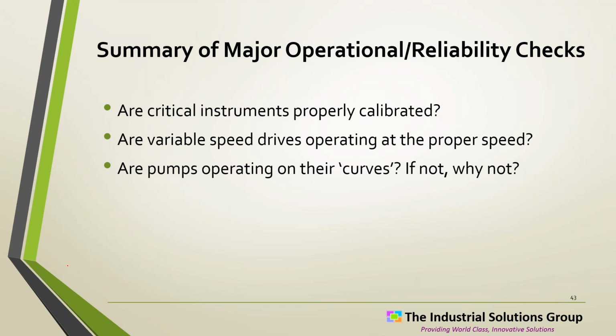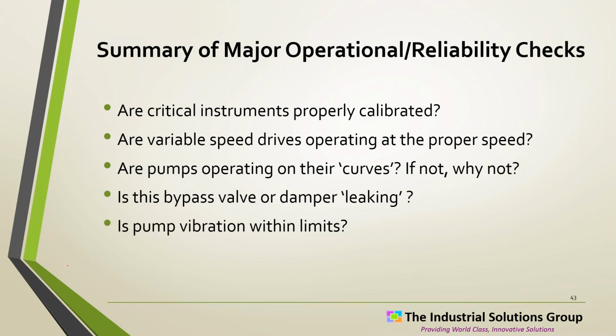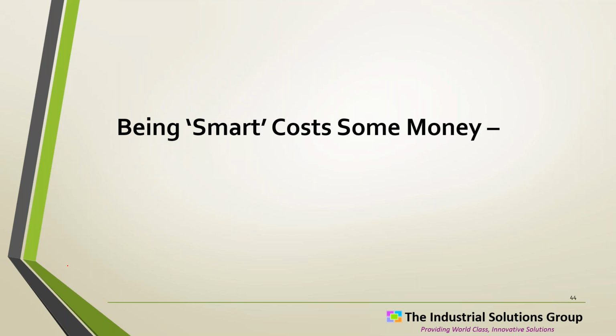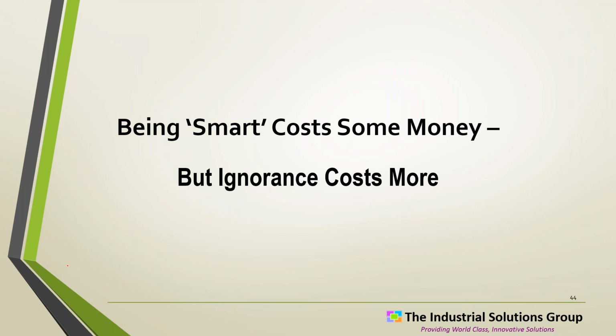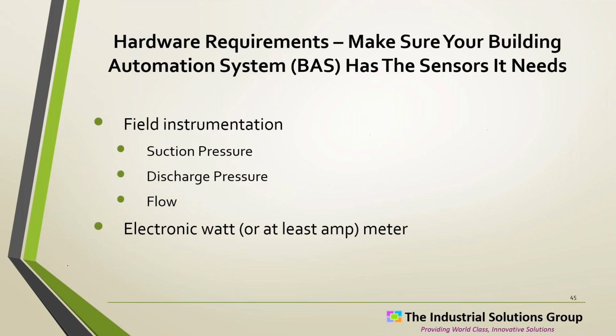Why is that an issue? Energy costs are higher year-round, but the big thing is you start getting the heat of the summer, are you really going to have enough cooling where you need it? The pumps operating on the curves, we've talked that, bypass valves leaking, dampers leaking, pump vibrations within limits. So, being smart costs some money. I think probably some brain power, really thinking through things as much as that. So that translates to money, some resources. But ignorance costs a lot more. Think about this pump with no impeller, it's $1 million a year. Simple example that cost a lot, but there are a lot of examples out there that are costing people money.